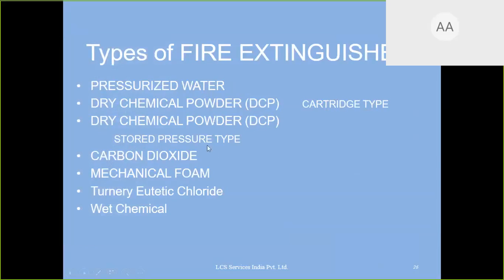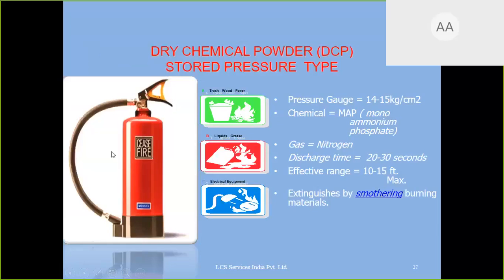The difference between the two: cartridge type, once you use, the whole powder will come out in one go. It will not stop in between. Here, whatever you press, it will come out, and the rest will be stored. This is the photo of the DCP, dry chemical powder stored pressure type, because there is a pressure gauge here, right? If the pressure gauge needle is in green, it means it is pressurized. If the needle is in red, it means there is no pressure. Powder will not come out.